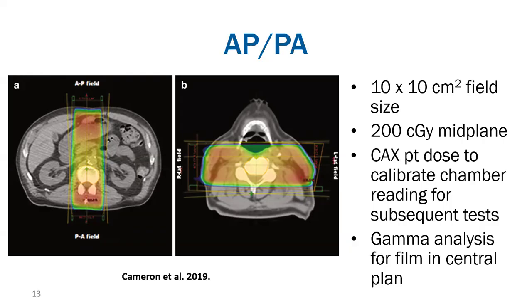really pushing our system to the limits with very modulated IMRT plans, right? We want to be able to have a baseline idea how our treatment planning system calculates dose, how accurately it calculates dose, right? So we start with a very simple, just AP/PA or lateral type plan, right? So the idea is that we can then see what the baseline agreement between the TPS and the measurement is. So then, as we start to increase the levels of complexity, we can start to see where our MLC model starts to fail. But we start with very simple plans.